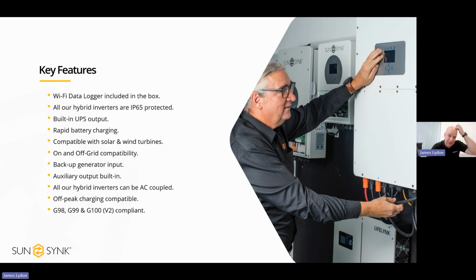So yeah, domestic over here, a lot of people are on feed-in tariffs still. So they can't change that string inverter. That needs to stay there, but we can AC couple that generation into our inverter. Off-peak charging compatible, so standard. So we've got 6 different time periods on the inverter UI where you can set when you want to charge it from the grid. We've got all the integrations with Octopus in the UK, and there's a lot more to follow. This is mainly for the north, but full G98, G99 and G100 compliance on all of our units.